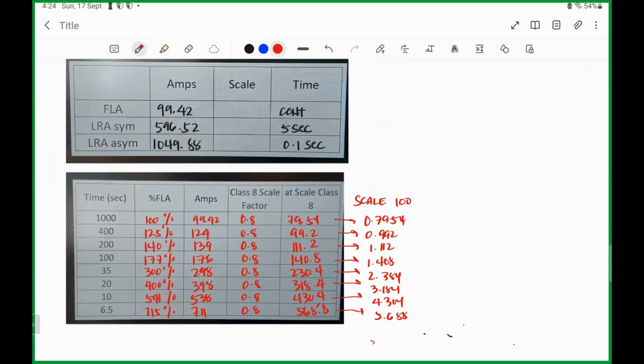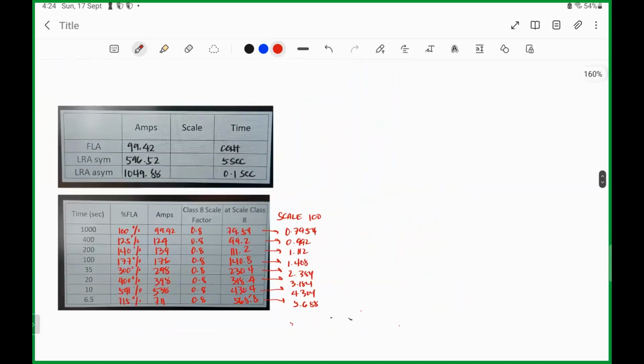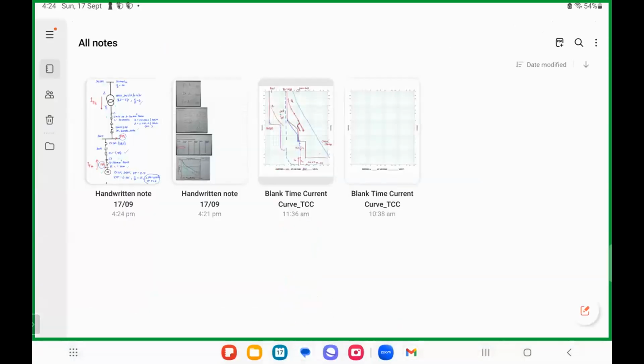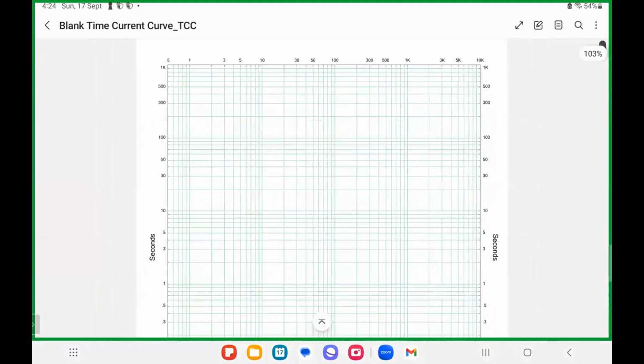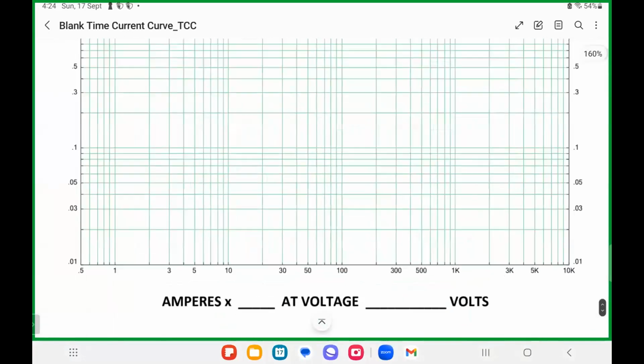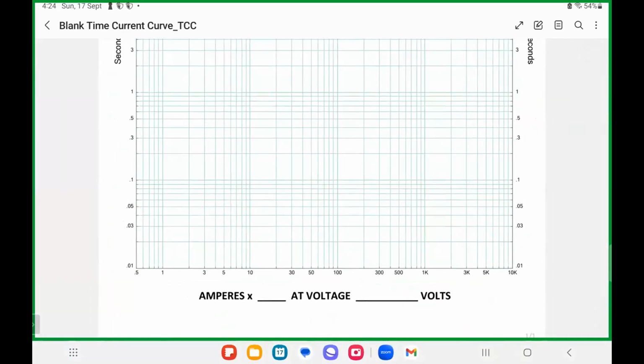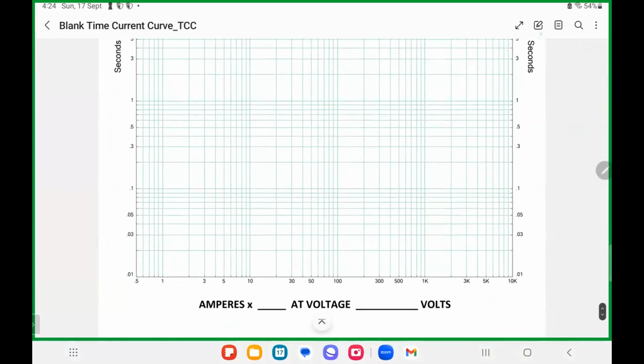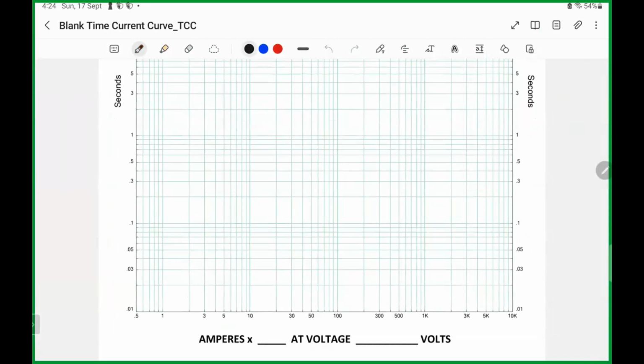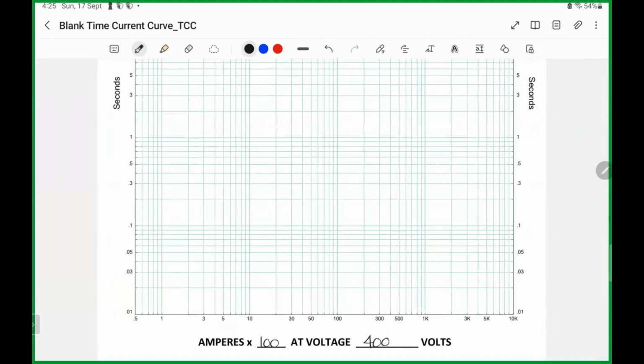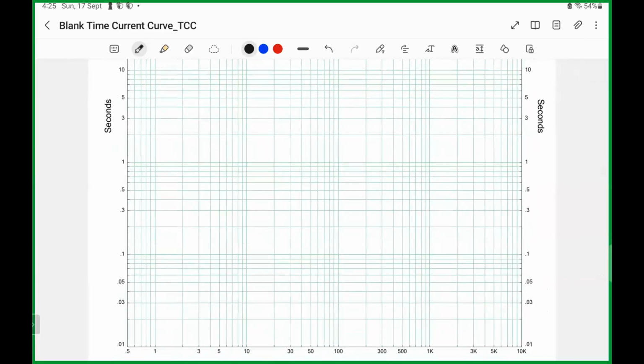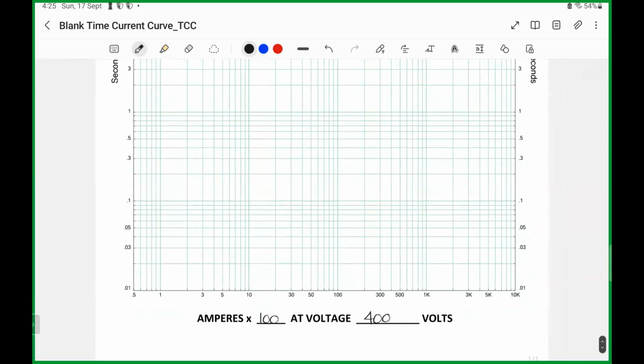So now, plotting tayo. So nakuha na natin lahat. Sige, sunod na lang natin mamaya para mas ma-appreciate niyo yung TCC. Mamaya may cable pa pala tayo at transformer. So let's plot first the motor. So dito sa motor, meron akong blank TCC. So ang gagamitin natin is yung amperes ko multiplied by 100, kasi yun yung scale na gagamitin ko. Ang reference voltage ko ngayon is the 400 volts. Okay? So now let's plot. Unahin natin yung motor. Hanapin natin yung FLA full load ampere na 99.42. Okay, scaled by 100.